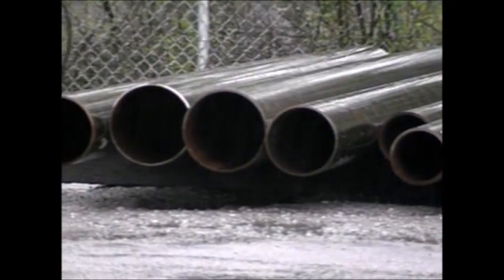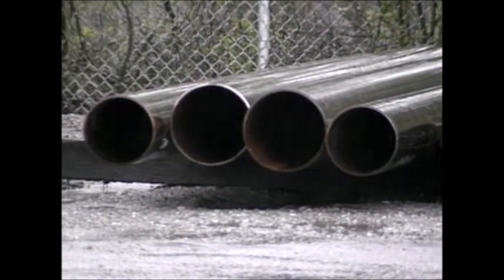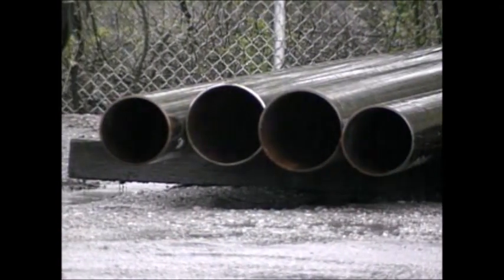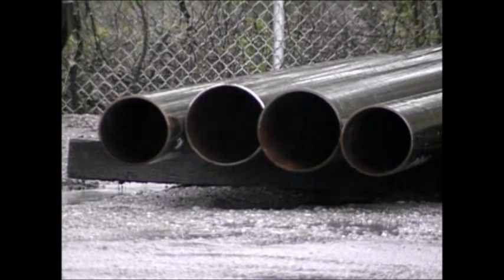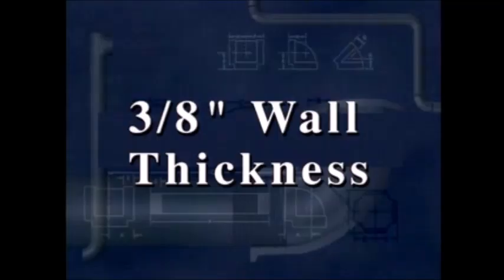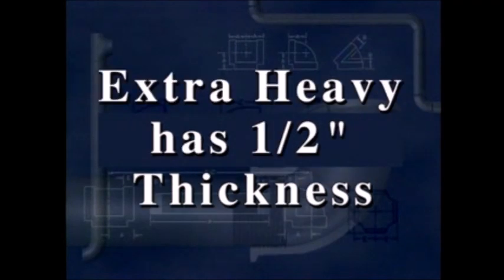For pipe that is larger than 12 inches in diameter, standard wall thickness is not a schedule, but means 3/8 of an inch wall thickness, whatever the OD. Likewise, extra heavy or extra strong pipe has 1/2 inch wall thickness, whatever the OD.